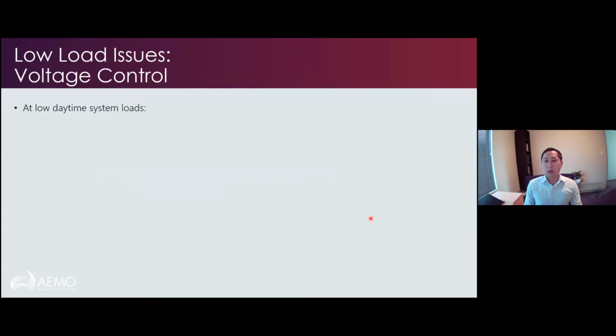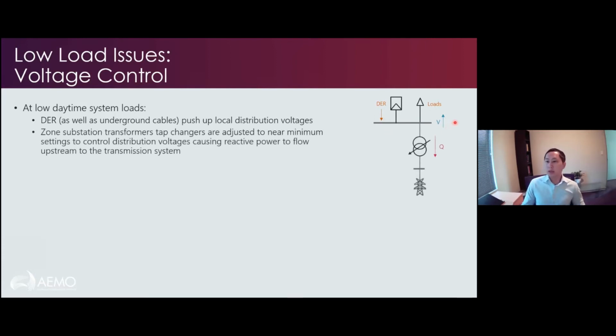In terms of voltage control, the issue we have at low daytime system loads is we have DER as well as underground cables, interestingly enough. WA has actually had large campaigns of undergrounding all the suburbs, and these cables just have excess capacitance, and they're pushing up local voltages in the middle of the day. So you can see here all this DER coming in, voltages coming up, and zone substation transformers, their tap changers are now moving to their minimum tap to control these voltages. As a result, all this reactive power is now moving out into the transmission system. So this is your distribution system. Now all this Q is going out into the transmission system upstream.